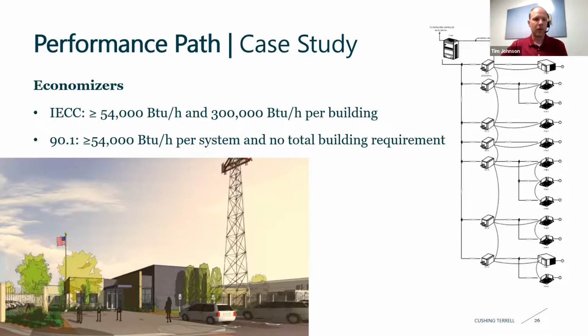Economizers, I already mentioned, are a big one. There have been jurisdictions that allow exceptions for dedicated outside air systems, not needing to comply with economizer requirements. Haven't seen that in IECC or 90.1 yet, but it seems like that's something that is being discussed. So currently IECC and 90.1 lets you have 54,000 BTUs, essentially 4.5 tons of cooling, in an individual unit before an economizer is required. And IECC has a limit to total building cooling capacity of 300,000 BTUs. So if you are over either of those, an economizer will be required on your equipment. And we have found if we're doing dedicated outside air with heat recovery, that generally performs very well compared to a baseline.